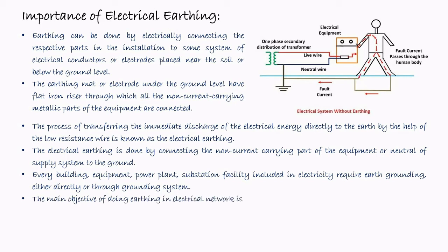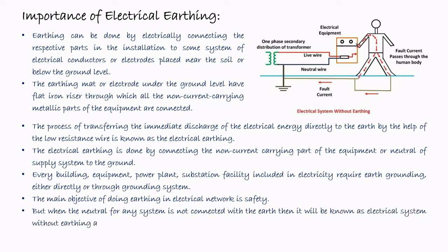The main objective of doing the earthing in an electrical network is safety. That is the main importance of electrical earthing. But when the neutral of any system is not connected to the earth, it is known as an electrical system without earthing, as depicted in the figure. So here we can see the figure again. If the earthing is not properly done for the equipment, then there may be a chance of electrical shock for human beings, although the supply system neutral terminals are properly grounded.